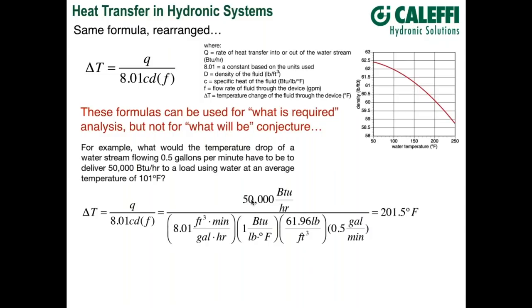What's a practical use of the relationship between flow, delta T, and heat transfer? One practical application is measuring both the rate at which heat is moving through a system and the total amount of heat moved over time — we do that with a heat meter or BTU meter. We need three things: the supply temperature going from the heat source to the load, the return temperature coming back, and an accurate flow measurement. High-precision temperature sensors matched with the instrument — directly immersed in the fluid to eliminate any air gap — allow the device to accurately calculate instantaneous rate of heat transfer.